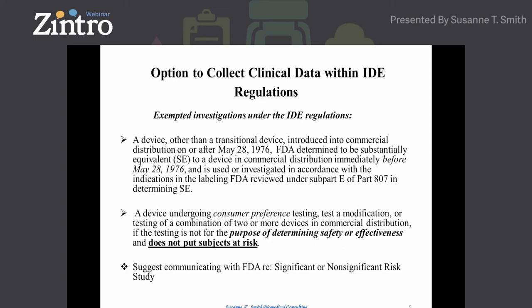I'd also like to point out that industry sometimes naively puts in the title of a clinical trial that they're going to evaluate a device for safety and effectiveness or efficacy. I would suggest you not use those terms in your clinical protocols on a commercial basis. Instead, use more generic language like clinical outcomes and complications.